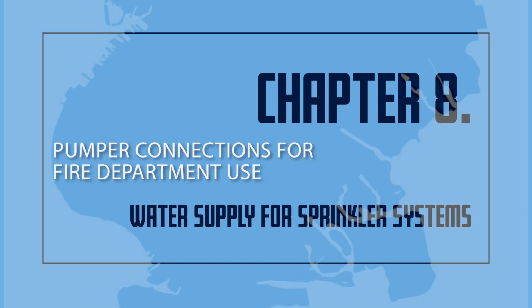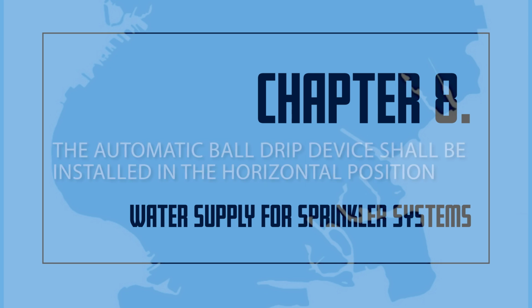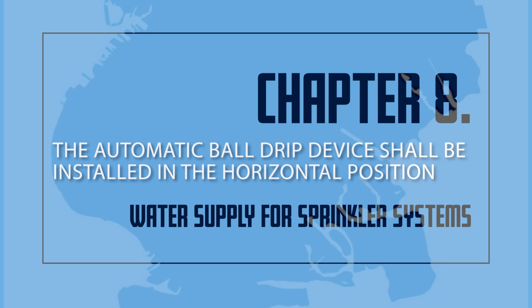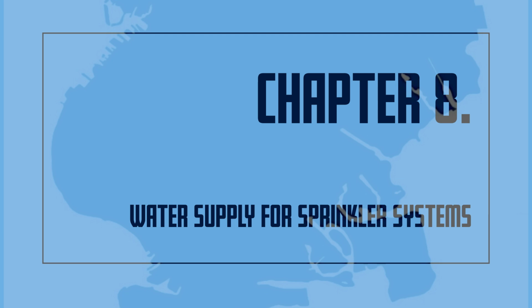Fire department connections must always be accessible. Each connection shall be fitted with a lower check valve. The lower check valve prevents the backflow of the private water supply into the fire department connection. The automatic ball drip device between the lower check valve and the outside fire department connection prevents water from building up in the piping and shall be installed in the horizontal position. This ball drip device makes sure that the fire department connection is not blocked by water which has frozen within the piping. If water freezes in the piping, the fire department will not be able to pump water into the system.